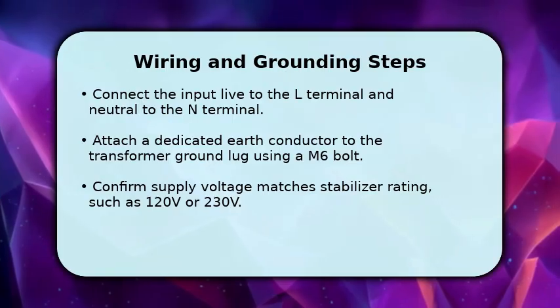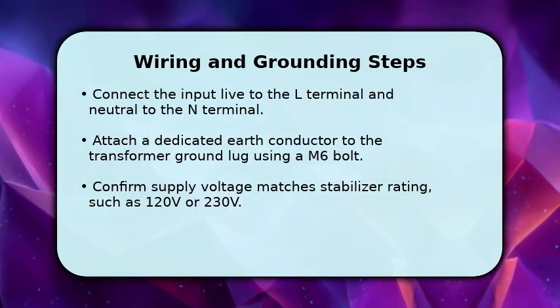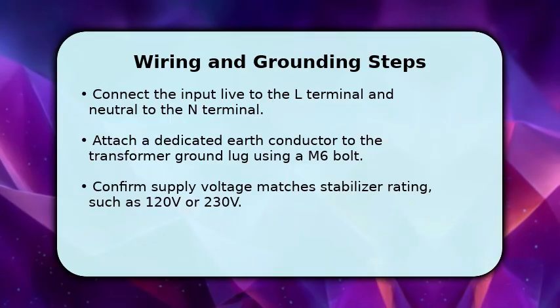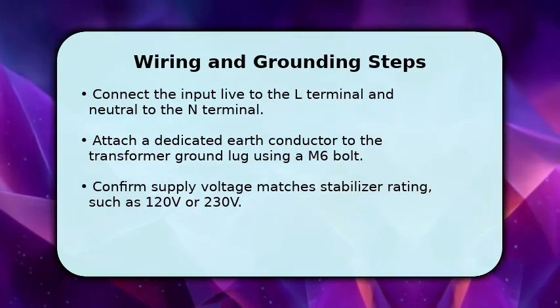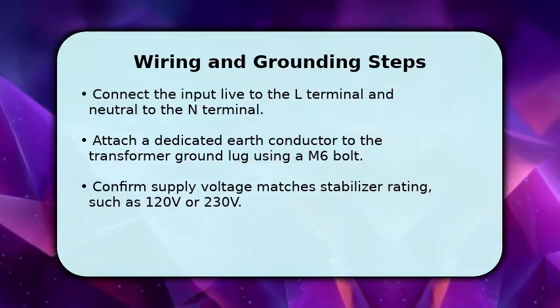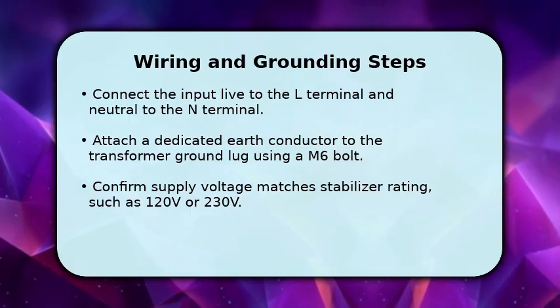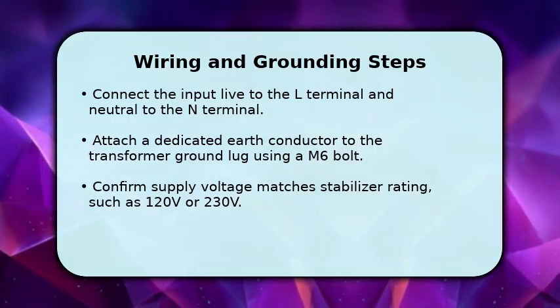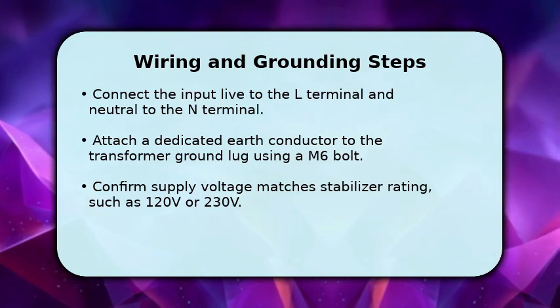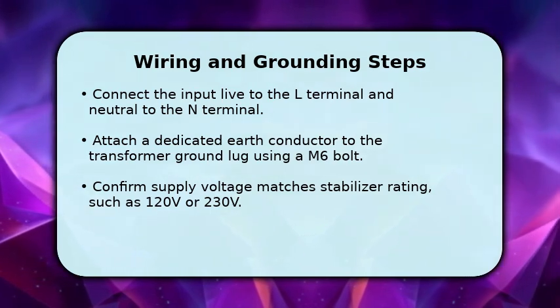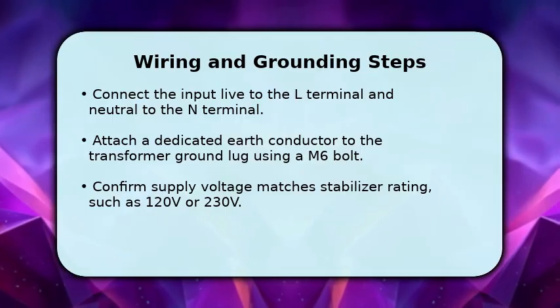Attach a dedicated earth conductor to the transformer ground lug using a M6 bolt and verify a low resistance path to building ground. Tighten all terminal screws to the manufacturer torque specification and secure cable glands to maintain IP protection. Label input and output conductors clearly for future service.